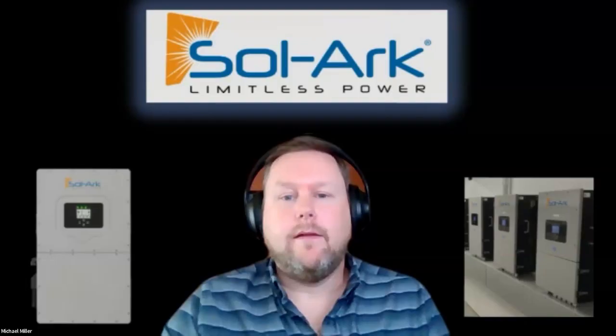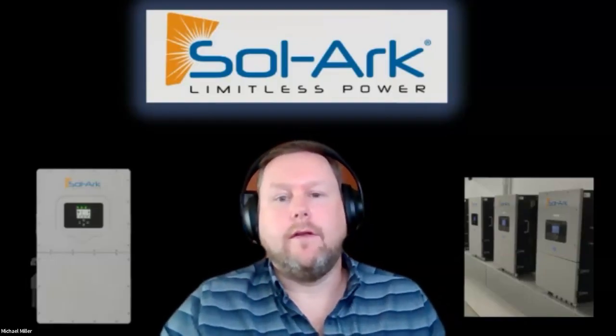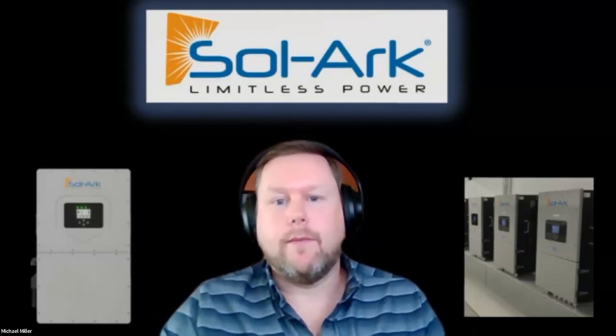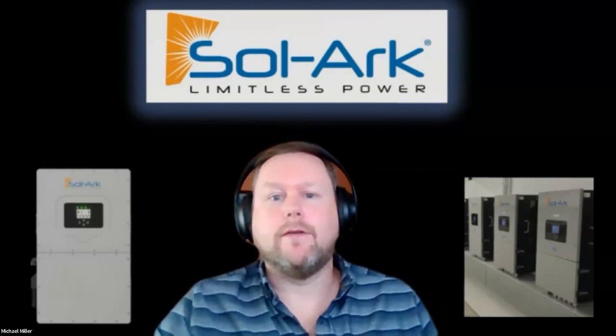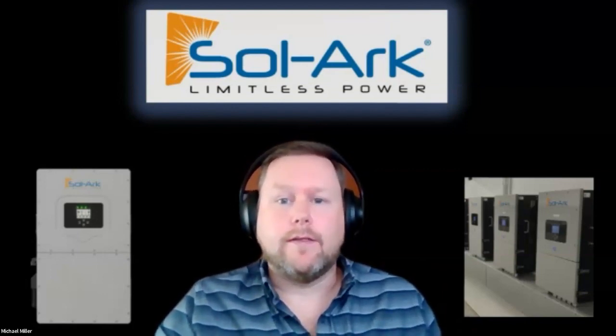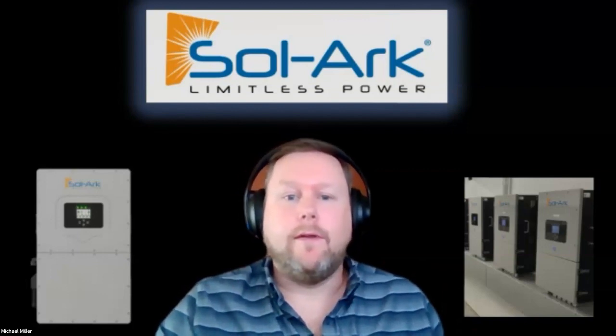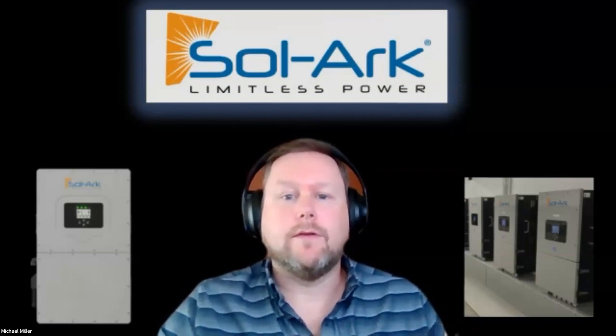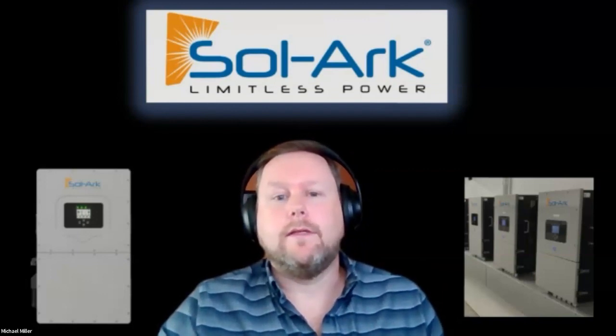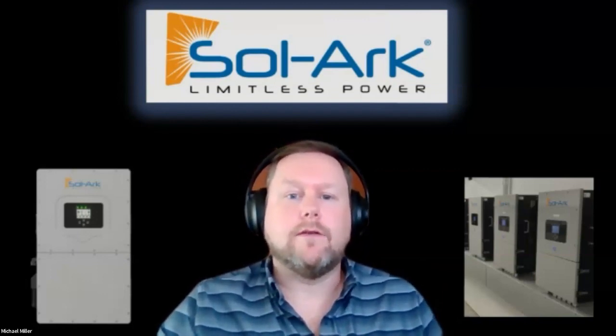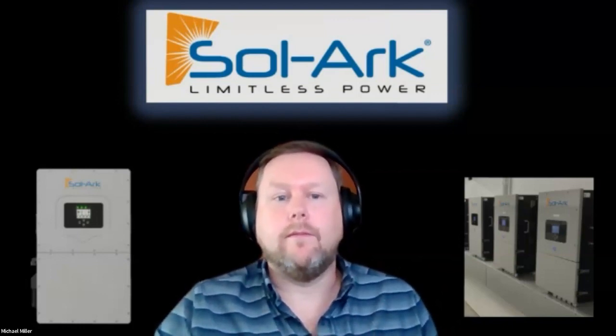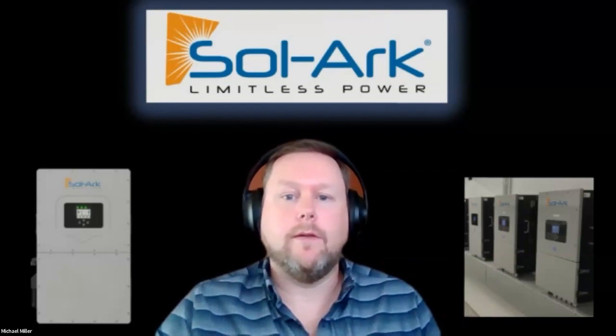You said there's built-in load shedding on the 15K—I thought the SL14 Lumin or similar would be needed for that, is that not correct? The built-in load shedding is more about: the grid is down, I want to drop my air conditioner, for example, or my battery's at a certain state of charge and I want to drop loads—as many as you could put on something that's 100 amps—or charge my EV when there's excess sun available. So that's the control in the inverter, while the smart load is more individualized circuit control, similar to a Lumin but with more inputs, and larger available inputs.